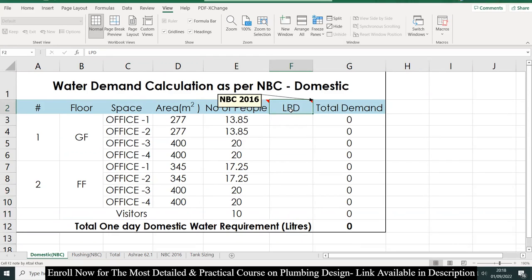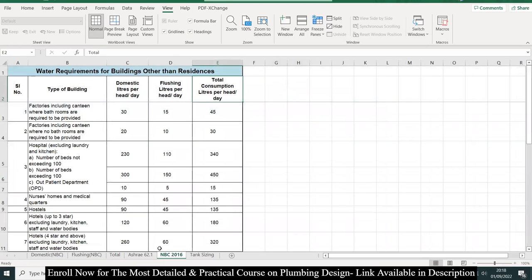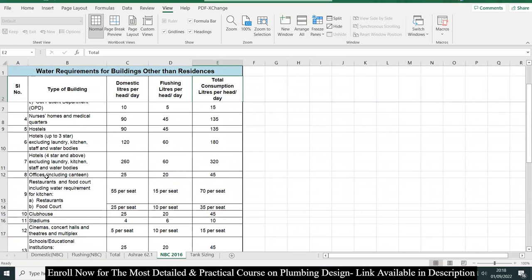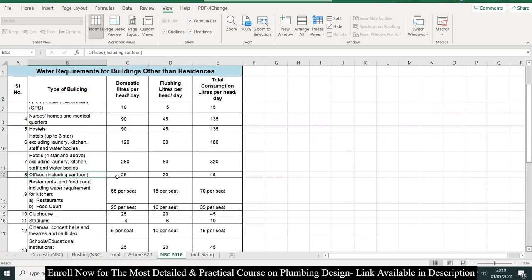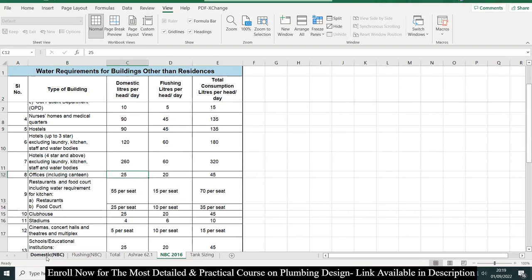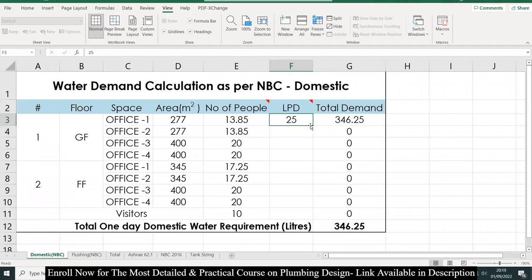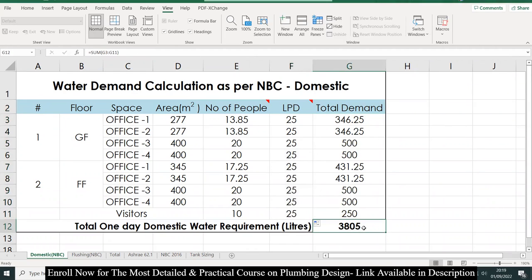The next input required is the LPD, that is liters per day — water consumption per day per person. This you will get from NBC 2016. Going to NBC 2016, we have different types of buildings. For an office building, under 'Offices including canteen,' we have domestic water demand, flushing, and total. For office, the domestic value is 25 liters per day per person. Entering 25 for all offices gives us the domestic demand for this building: 3805 liters.